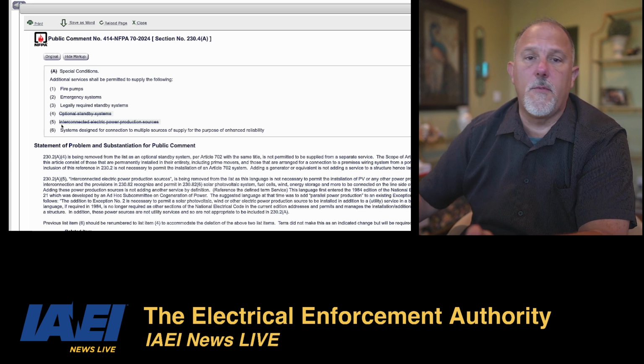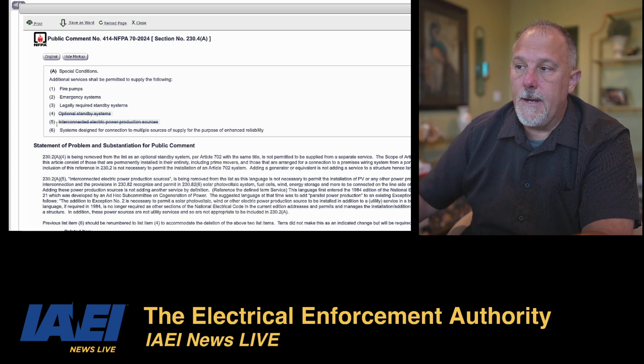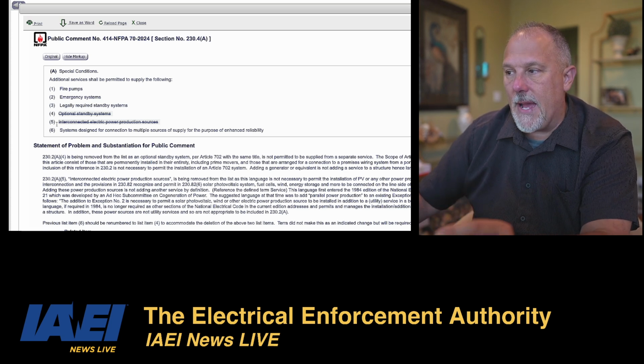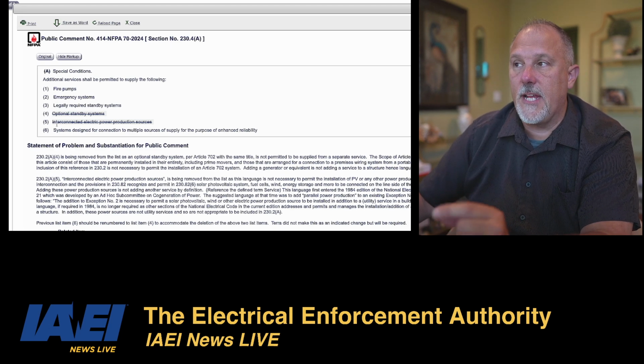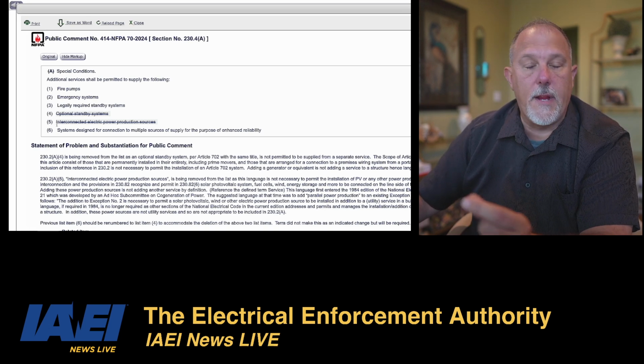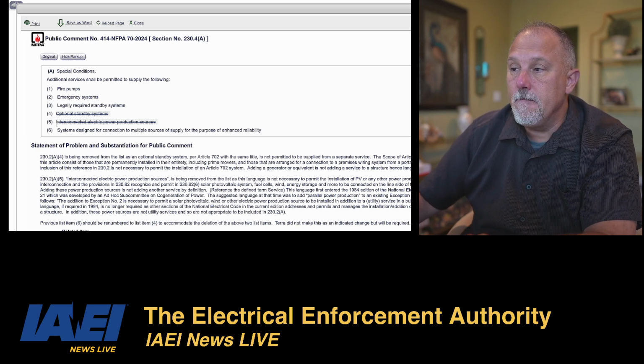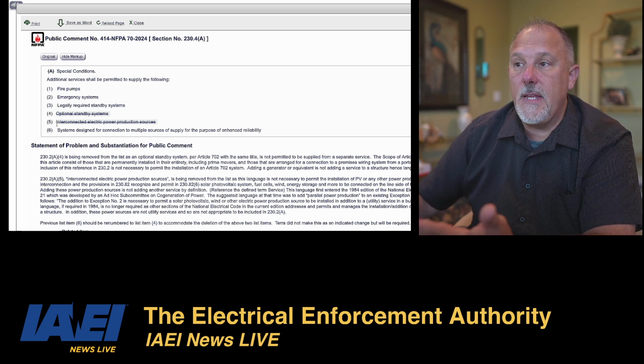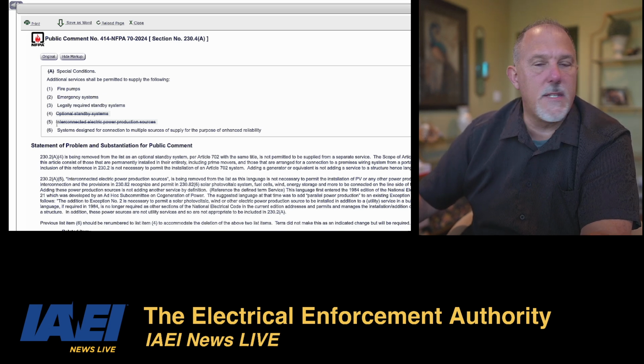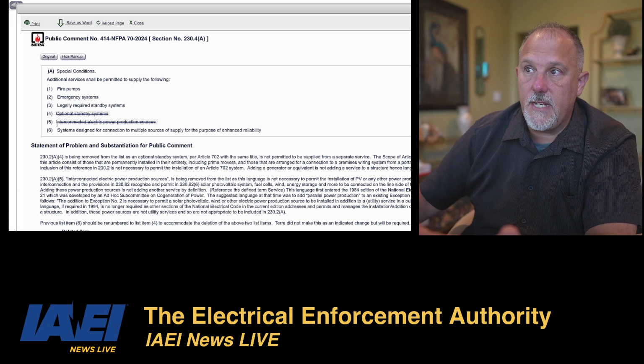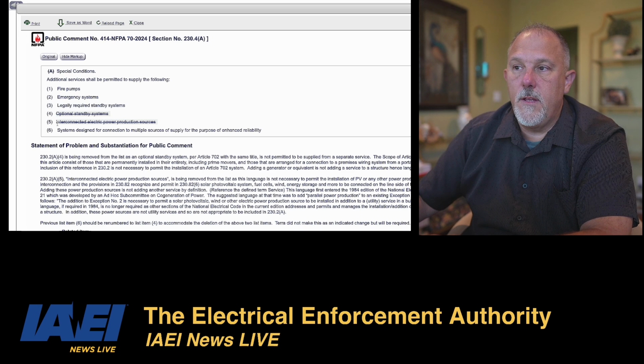And then I removed interconnected electric power production sources. That one was interesting. I went back to when it first went into the National Electrical Code. I believe it was the 1984 NEC. And the reason it was put in the first place was because they said that it was needed to permit photovoltaic, wind, or other electric power production sources to be installed in parallel with a utility. Well, those sources are not services, so it doesn't make sense that they would need to be in special conditions, because if you're going to have an additional service, it's not required when you are installing those other systems.